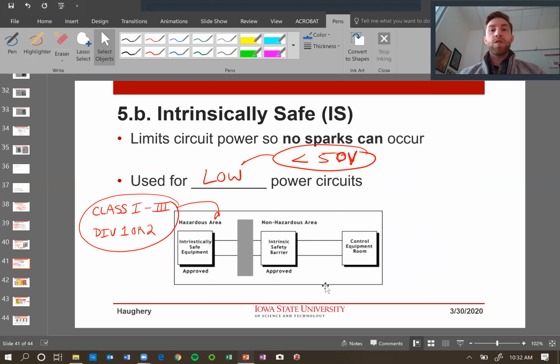And then we have intrinsically safe, which is our low voltage. You can literally have two bare wires, theoretically, sparking in open air in that explosive environment, and an intrinsically safe barrier will keep that incident energy at a low enough level that you will not get a spark to explode the environment. And so that's where we usually see those in low voltage scenarios where we're just looking at the sensors in that environment.